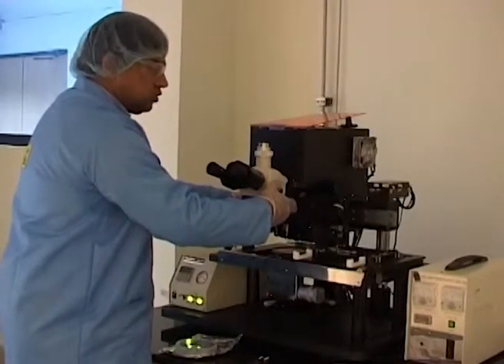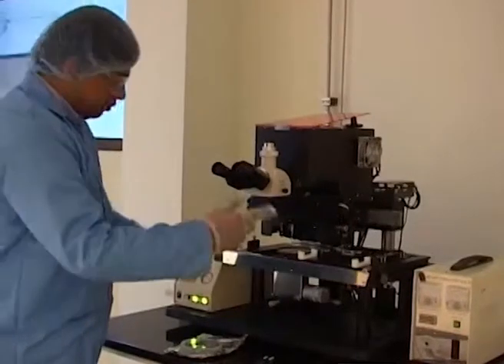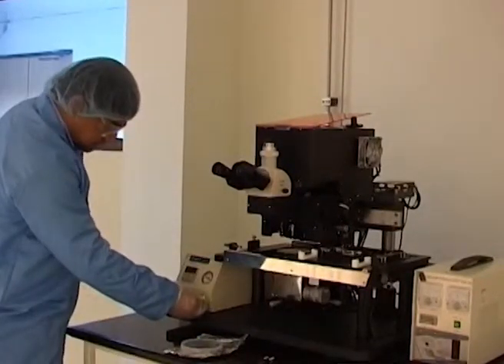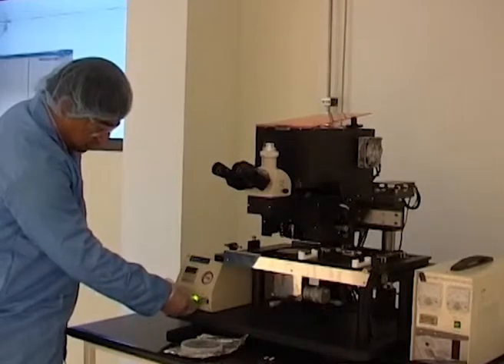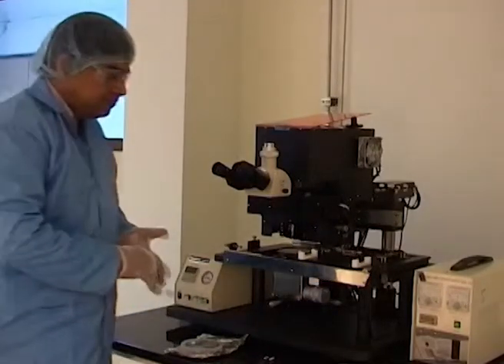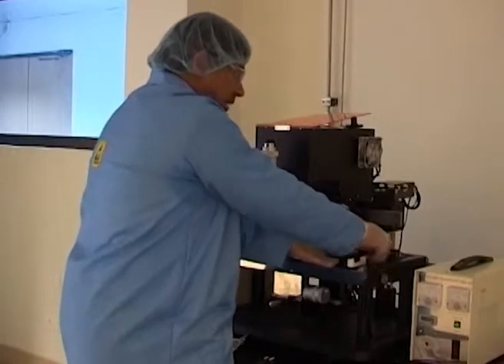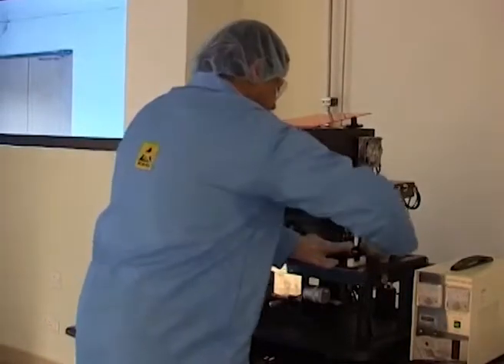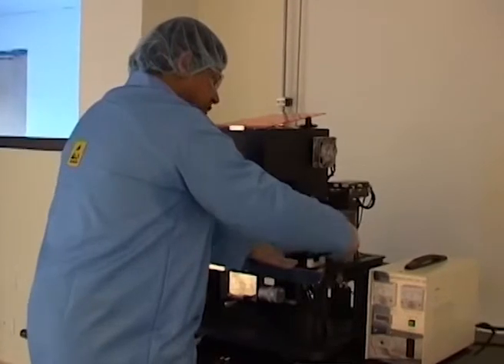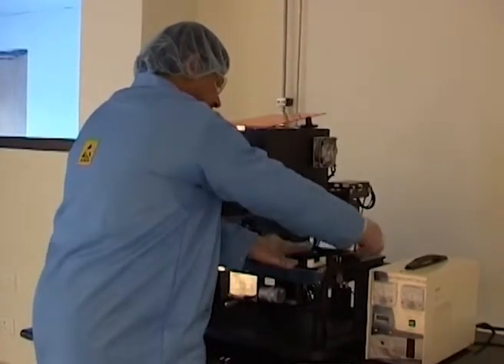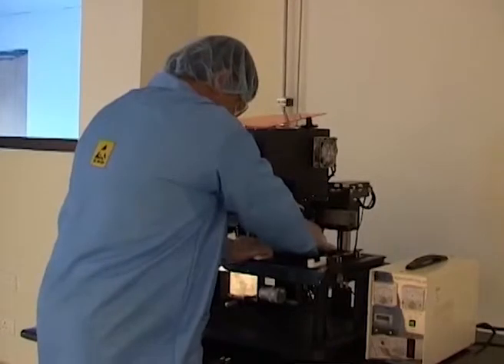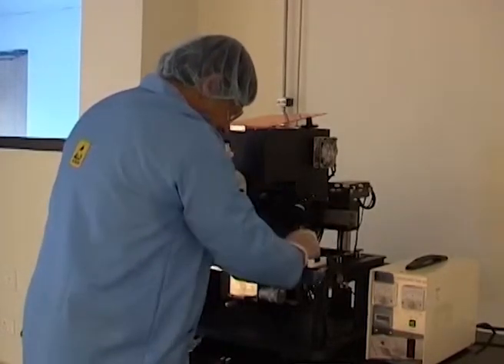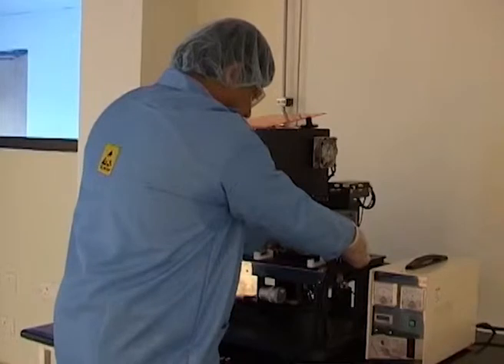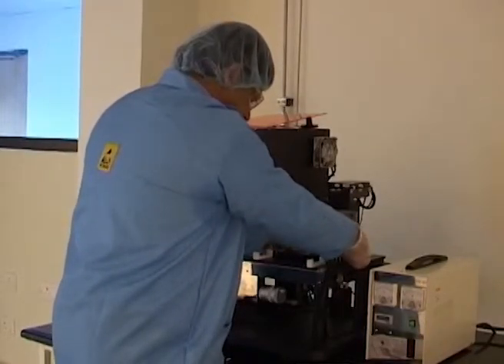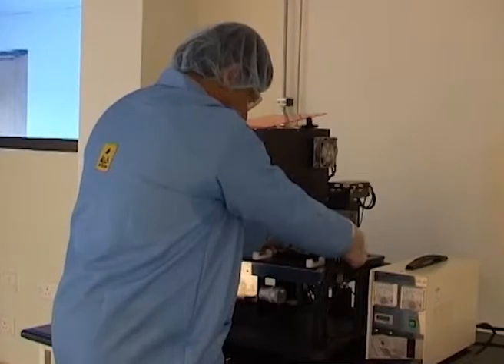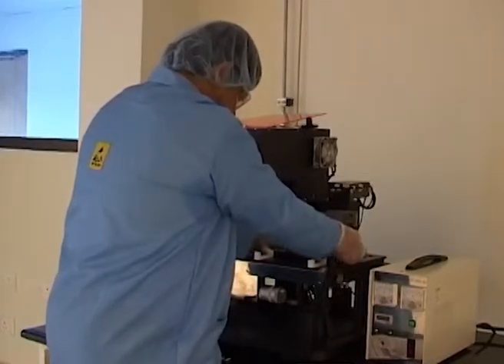We also need to reverse the sequence to pull out the mask. We need to switch off the wafer holder as well as the mask vacuum, and pull back the mask in a pretty much similar manner as we had loaded it before. So these bolts need to be untied so that they lose grip on the top of this wafer holder. Slowly move the holder back in its place.